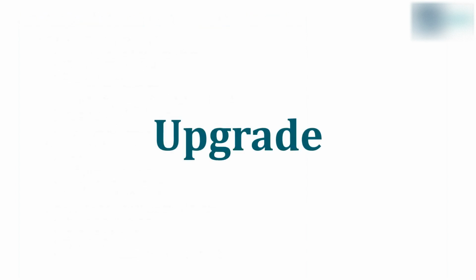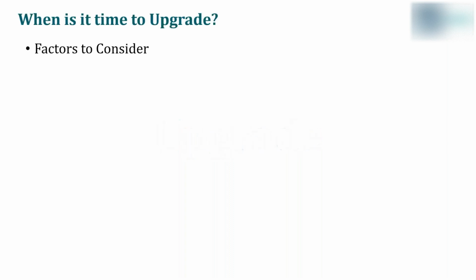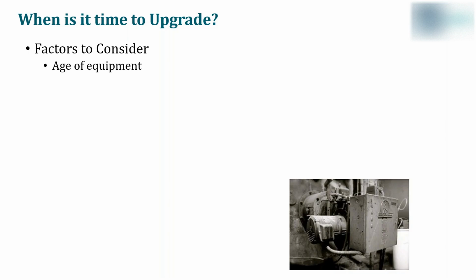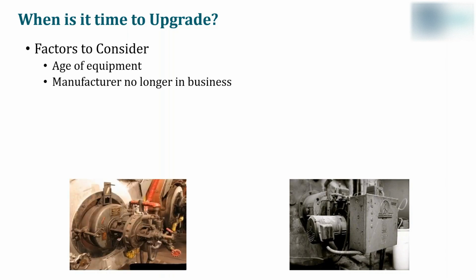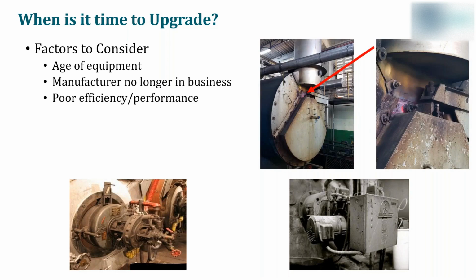Now, before we contemplate quoting a retrofit, I think it's important to look at a few examples of when it may be time to just upgrade the equipment entirely. Factors to consider when a retrofit may not be the best option. First, the age of the equipment could be at a point that the components become very expensive or difficult to procure. Second, manufacturers no longer in business. Over the past 10 years, many of you have experienced this with certain manufacturers closing the doors and parts are no longer available.